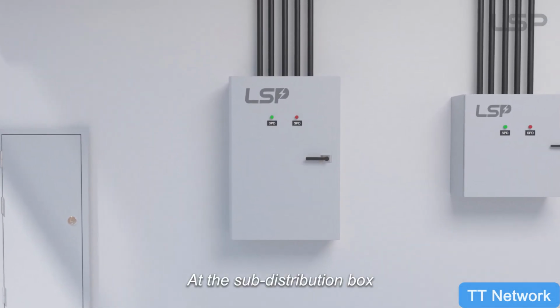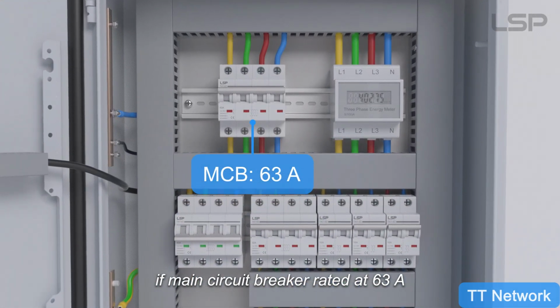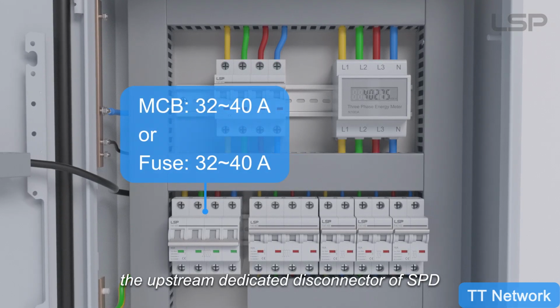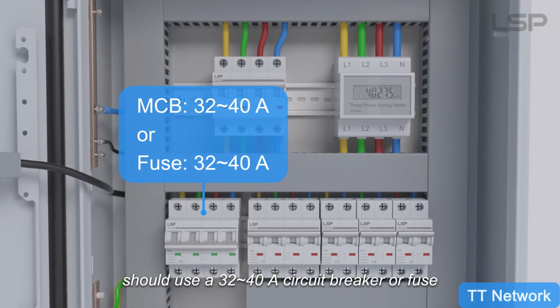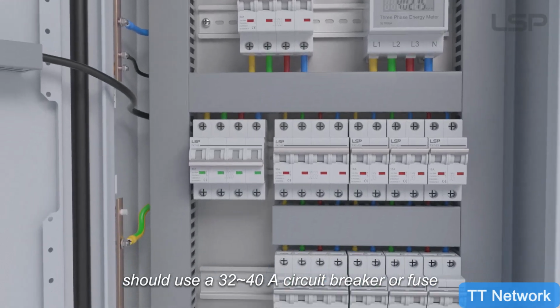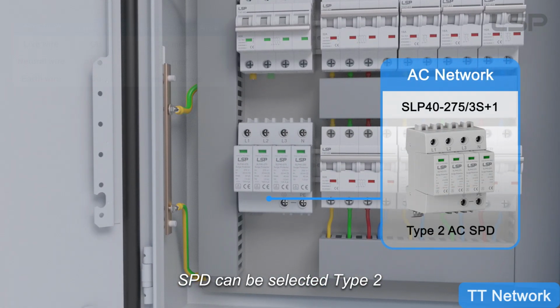At the sub-distribution box, if the main circuit breaker is rated at 63 amps, the upstream dedicated disconnector of SPD should use a 32 to 40 amp circuit breaker or fuse. SPD can be selected type 2.